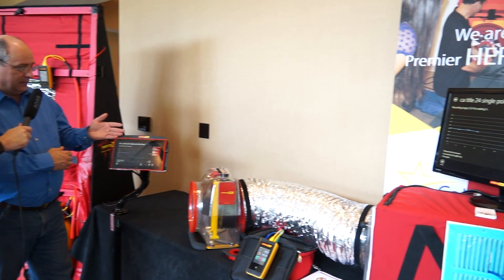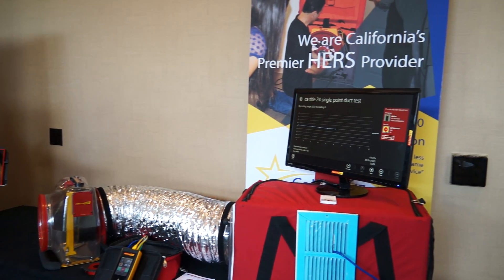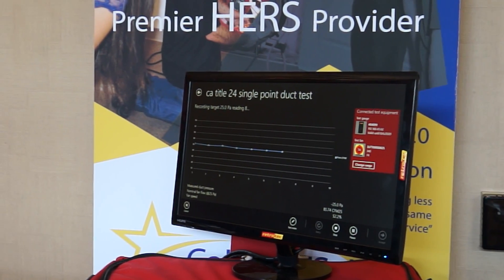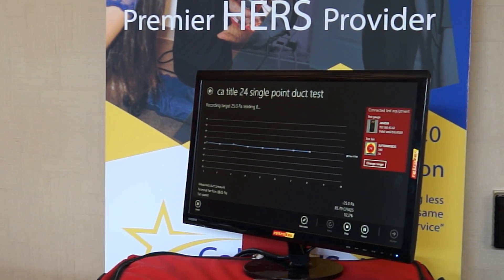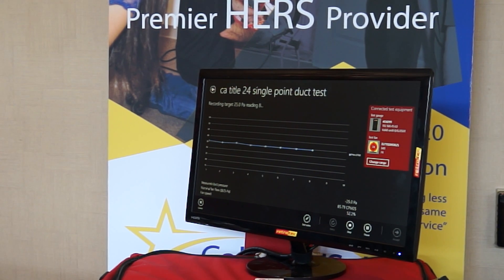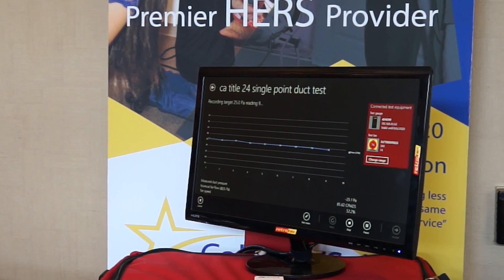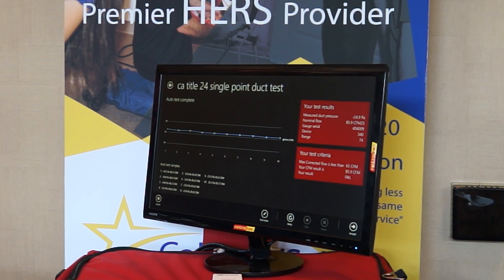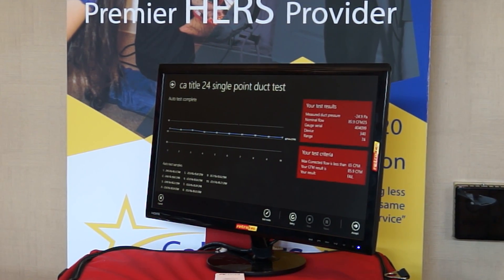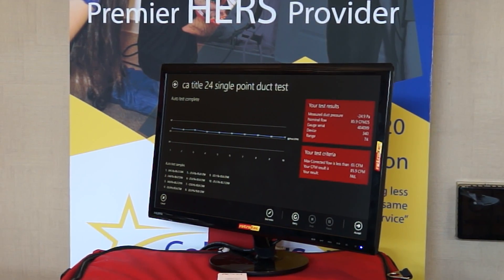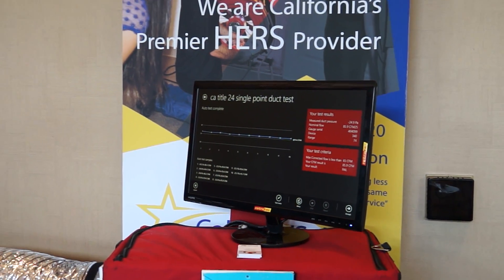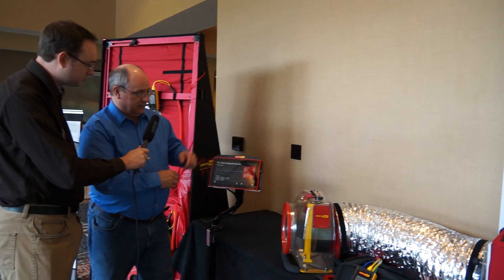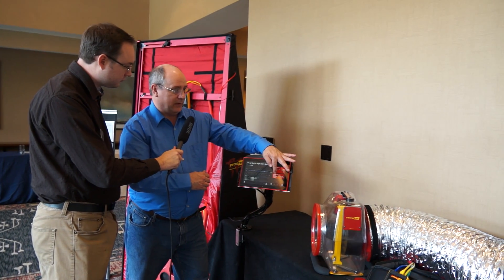So we actually have the test going through and it's following the parameters for Title 24. You can see it's going through a 10-point test for so many seconds per acquisition. It gives me an average when it's done — and that's how quick it was. If I'm looking for any outliers, or if one of my covers fell off on my registers, I can see an outlier here and just literally redo the test.